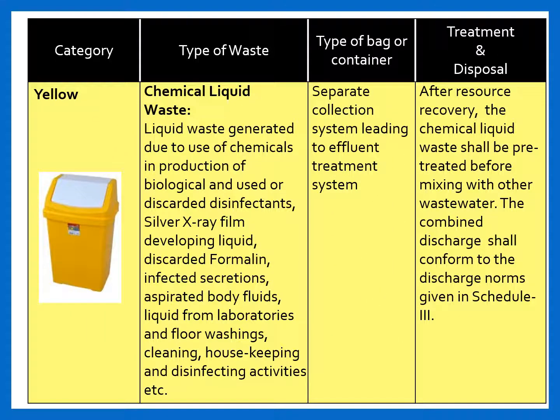Similarly, liquid waste generated due to chemicals in the production of biologicals and used or discarded disinfectants — including silver X-ray film developing liquid, discarded formalin, infected secretions, aspirated body fluids, liquids from laboratories, and floor washing, cleaning, housekeeping, and disinfectant activities — should have a separate collection system leading to an effluent treatment plant. The chemical liquid waste shall be pre-treated before mixing with general wastewater, and the combined discharge shall conform to the discharge norms given in Schedule 3.